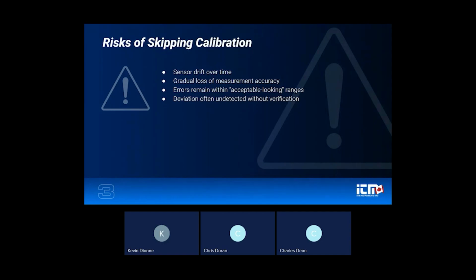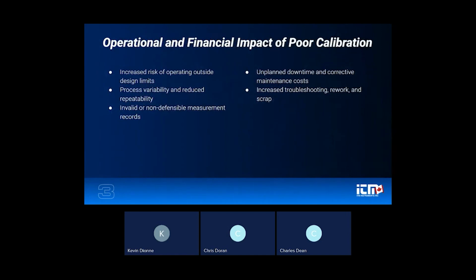The issue is that this deviation often remains undetected if you're not doing your calibration. And without verification, there's no objective way to confirm whether the instrument is still performing within its specified tolerance for your application. Over time, that unnoticed deviation becomes embedded in the process, and your measurement confidence slowly erodes without anyone realizing it.